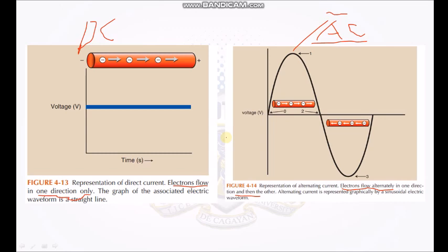It's important that when it comes to our X-ray tube, inside the X-ray tube we only operate through direct current. Even if the electricity coming in from the main power supply is AC, alternating current, the current and the voltage are converted to direct current, and that is through rectification.